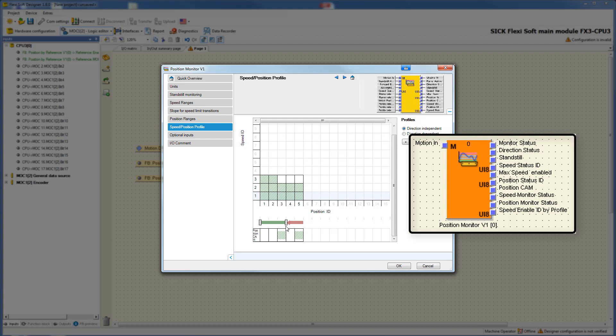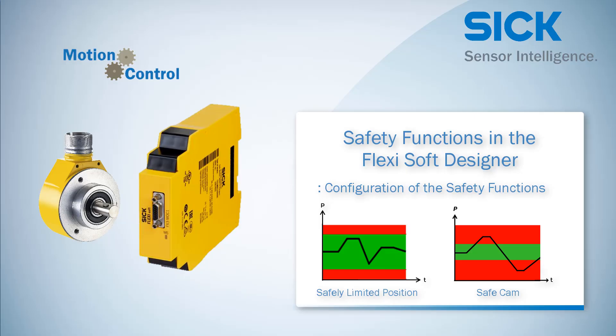The position monitor function block has no motion output. If the drive moves in a forbidden area or direction, an error reaction is generated and the output position monitor status goes low. This output can be connected, for example, to a safe stop function block. That's it for the tutorial about the safety functions safely limited position and safe cam. Now you've learned the functionalities and how to configure these safety functions in the FlexiSoft Designer.